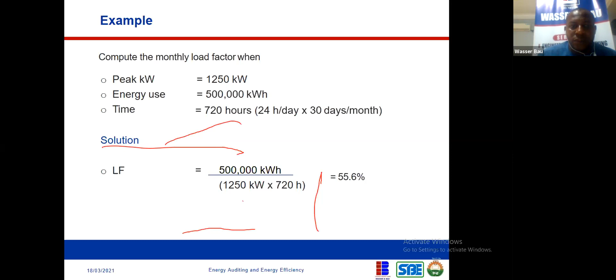So, if you remember the formula for our load factor, it is the energy consumption divided by the peak demand and the hours, or time, over the period that you want to determine. It can be a month, a day, or a year, but in this case we are looking at a month. So if you're looking at the hours in a month, you have 720 hours. To compute your load factor, you take the energy that you actually use within that month divided by the peak demand times the hours in that month.